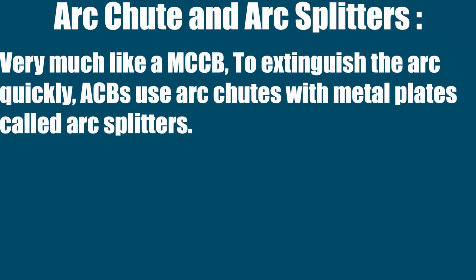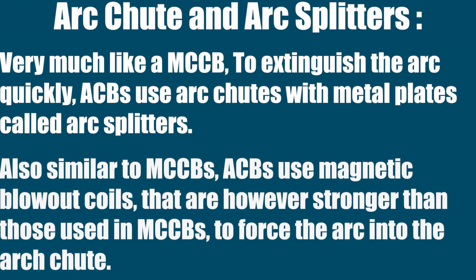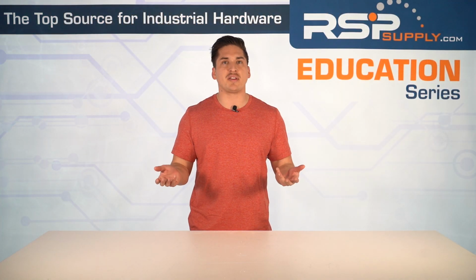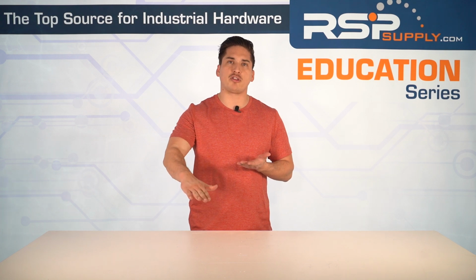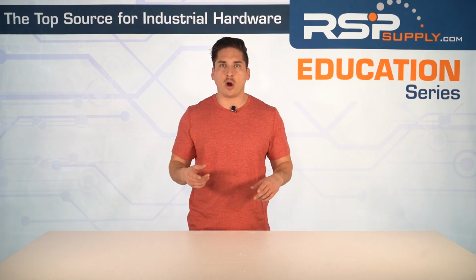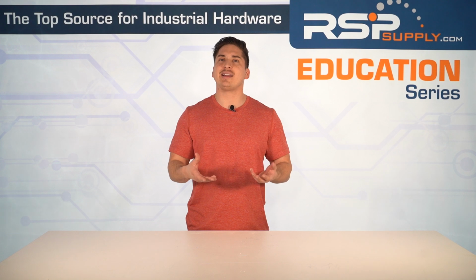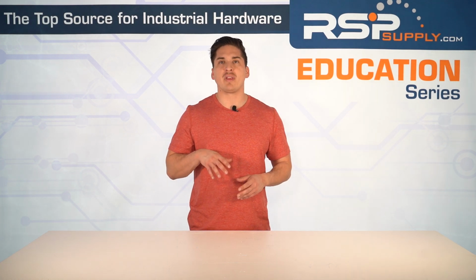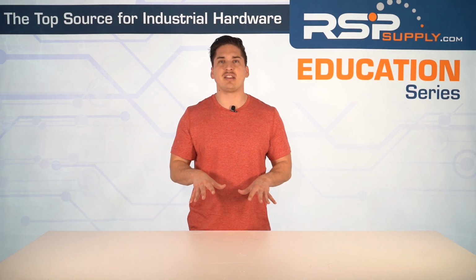Next, arc chutes and arc splitters in ACBs, a lot like a molded case circuit breaker. To extinguish the arc quickly, air circuit breakers use arc chutes with metal plates called arc splitters. Also similar to MCCBs, air circuit breakers use magnetic blowout coils. These are, however, stronger than those used in MCCBs, and these force the arc into the arc chute. In some models, there are even puffers or air blasts that physically push the arc away. The arc is then drawn into the arc chute because of the natural movement of ionized gases and electromagnetic forces. ACBs use longer arc chutes, though, with more arc splitter plates than an MCCB uses.